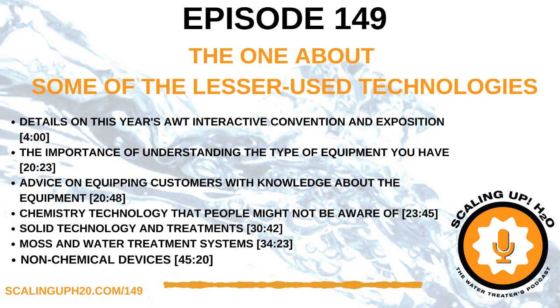As it cleans up, let's say the boiler system, it's carried off to the steam system and then to the condensate system. You're looking for a result all the way at the end, in the return condensate, of a free residual. All along, you're checking your iron levels and things like that. But if you're covering up your metal, you eliminate all the issues you'd otherwise have.